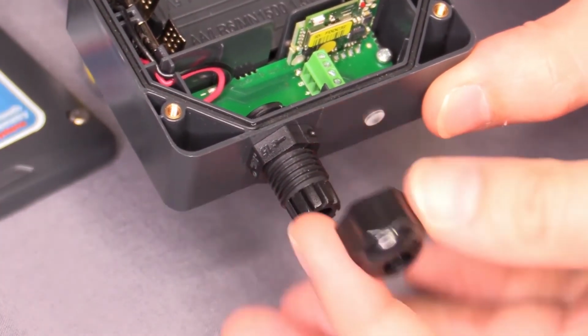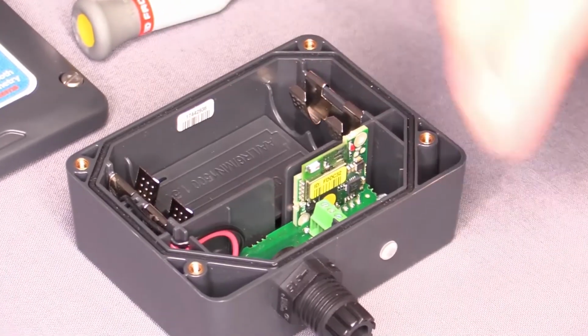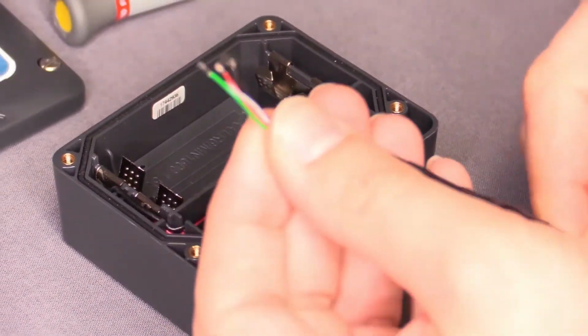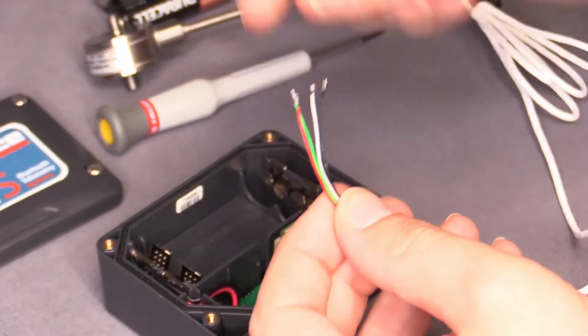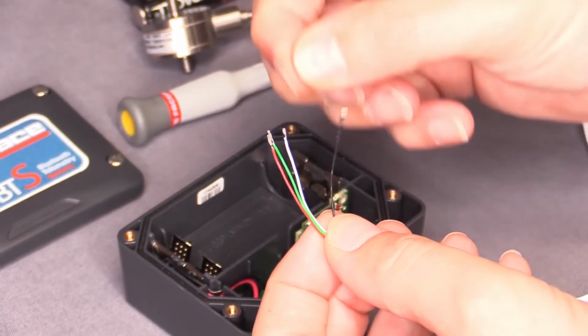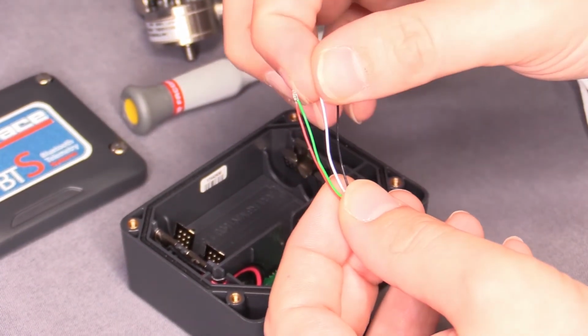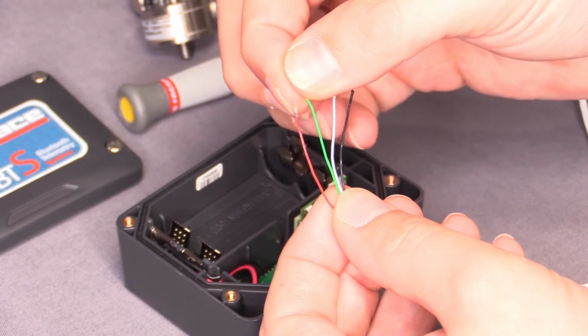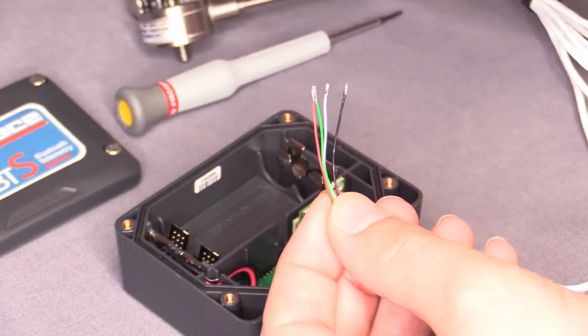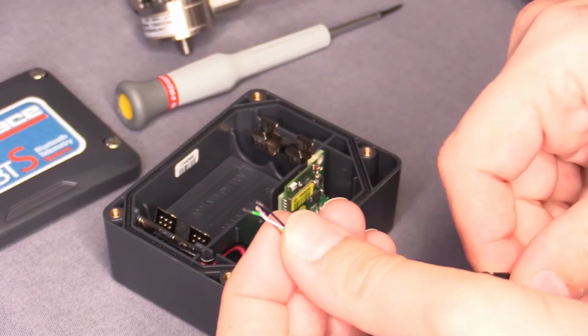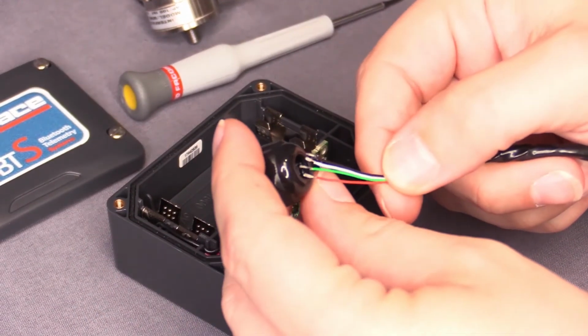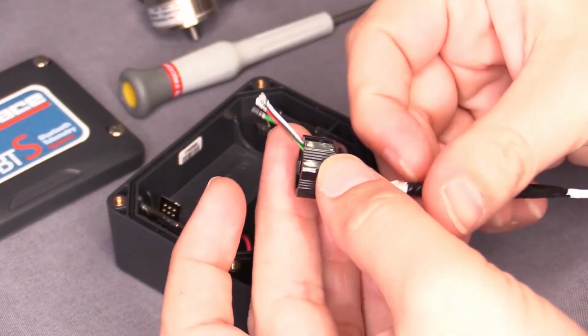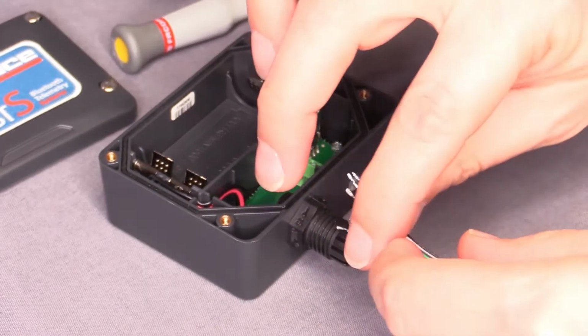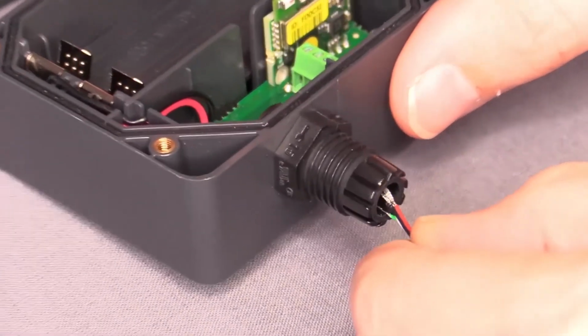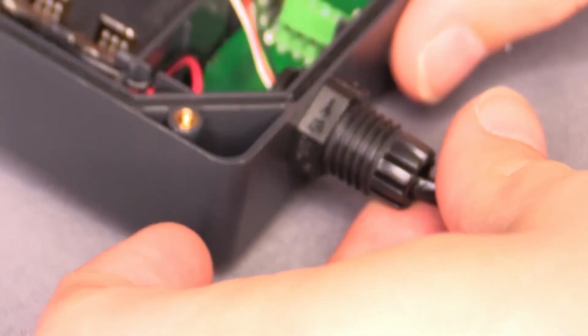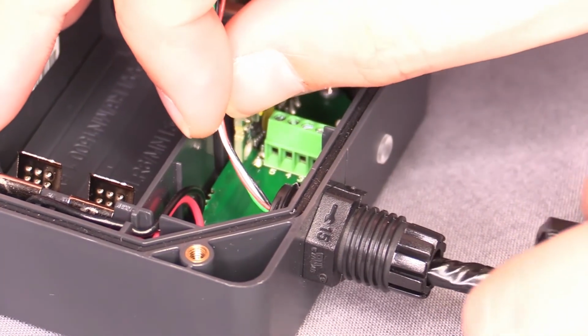I'm going to take off the gland nut. And we have our four wires from the load cell. So we have our negative excitation, our negative signal, our positive signal, and our positive excitation. So these four wires are going to go through the gland nut and then into the BTS AM1 module. You'll see them pop through here. You don't have to tighten this all the way yet.